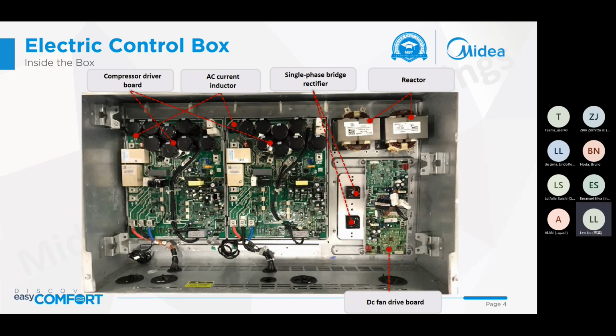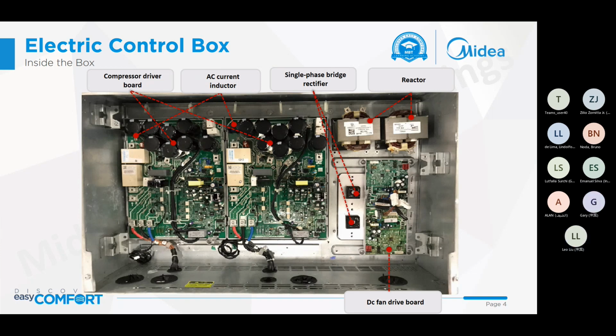Inside the control box, we can see the compressor driver board. This control box with two compressor driver boards is for big capacity, so each compressor has one compressor drive board. On the compressor drive board is the AC current inductor. To the right side is the single phase bridge rectifier, which is the rectifier for the fan motor. And in the right corner is the reactor, two reactors.